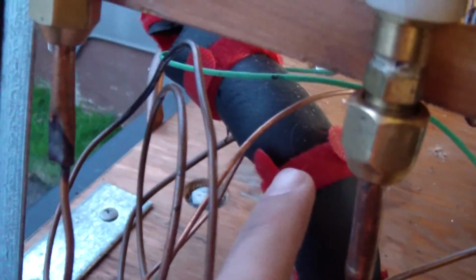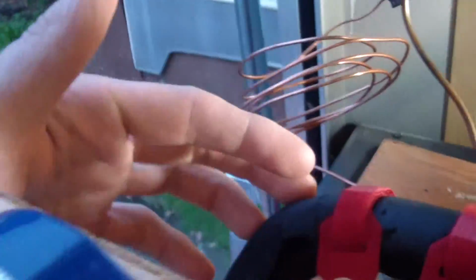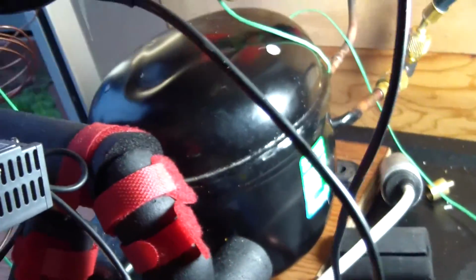We have a stainless steel pan there with a mixture of propylene glycol and water, about 10% propylene glycol. Starts to freeze at about 26 degrees. There's just a copper loop in there. And then the suction line comes back up. Like I said, the heat interchanger there loops up around and then back into the compressor.